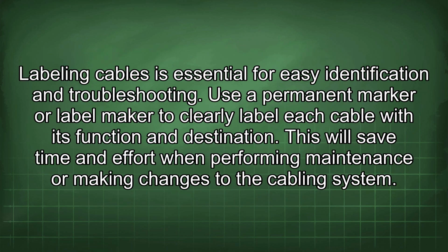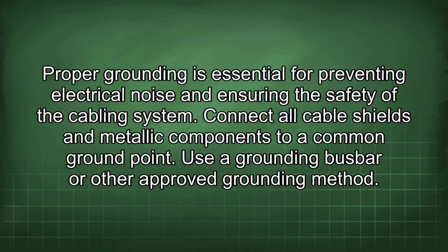Labeling cables is essential for easy identification and troubleshooting. Use a permanent marker or label maker to clearly label each cable with its function and destination. This will save time and effort when performing maintenance or making changes to the cabling system. Proper grounding is essential for preventing electrical noise and ensuring the safety of the cabling system. Connect all cable shields and metallic components to a common ground point. Use a grounding busbar or other approved grounding method.